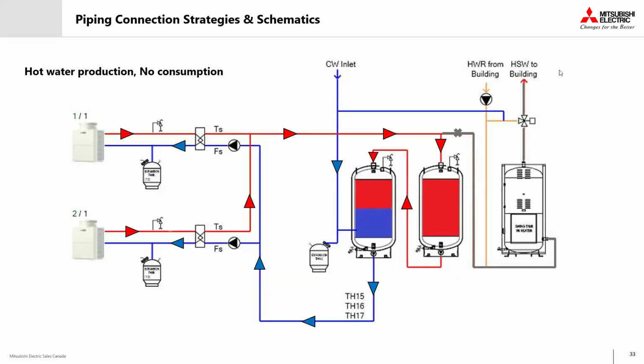Our storage tanks, a lot of the time in these low recovery, high storage systems, can be looked at as thermal batteries, if you will. So in this scenario, we're charging our thermal batteries, so we're charging our storage. All of that hot water that we're producing from our heat pumps is directly charged into those storage tanks, so there's plenty of supply available for upcoming peak demand. Sensor data and controls ensure that the heat pumps stop charging when we meet our tank temperature set points.